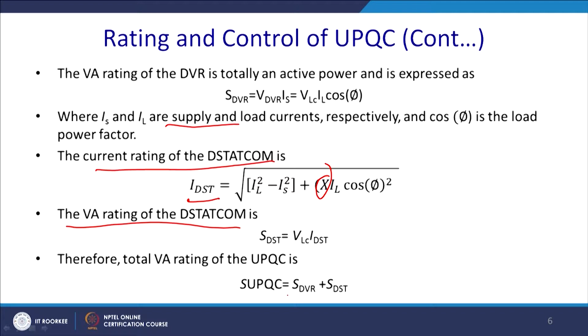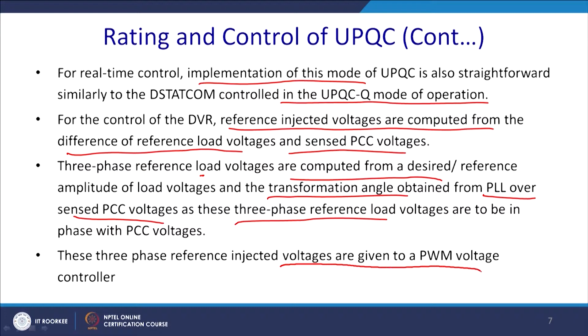The real time control and implementation of this UPQC is straightforward, similar to what we have seen in case of the UPQC Q, that is the D-STATCOM control in the UPQC mode of operation. For the control of the DVR, the reference injected voltages are computed from the reference load voltages sensed at the point of common coupling. It is the same here. The three phase reference load voltages are computed from a desired reference amplitude of the load voltages and the transformation angle obtained from PLL over the sensed PCC voltage, as the three phase reference load voltages are to be in phase with the PCC. These three phase reference injected voltages are given to the PWM voltage controller to generate the reference voltage, and this will be injected with the series compensator.